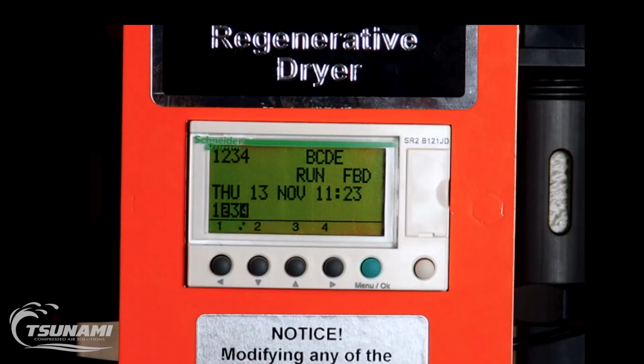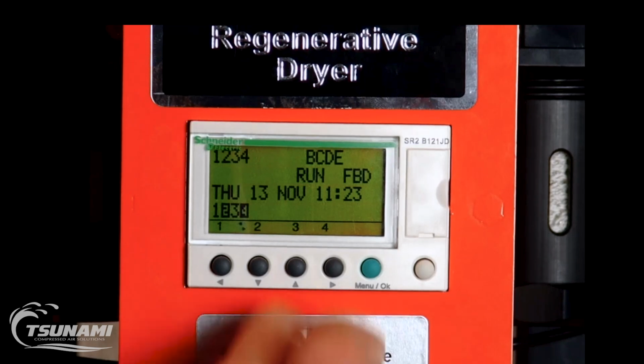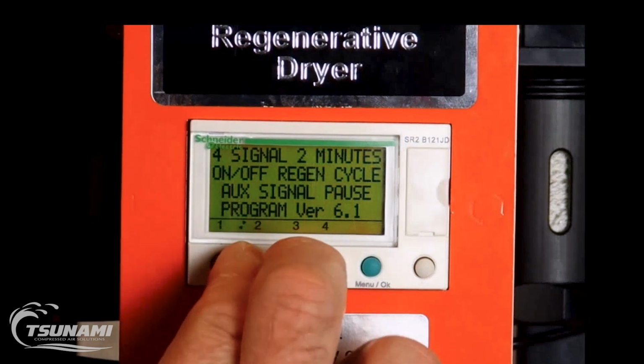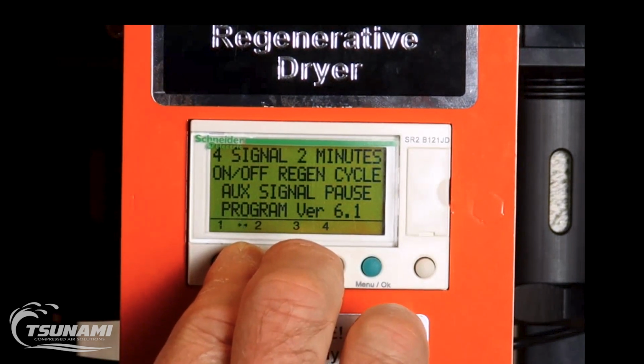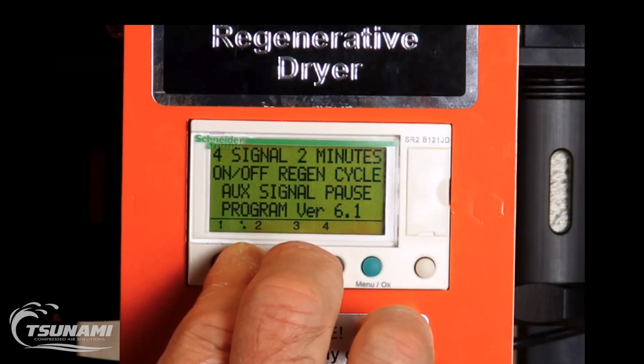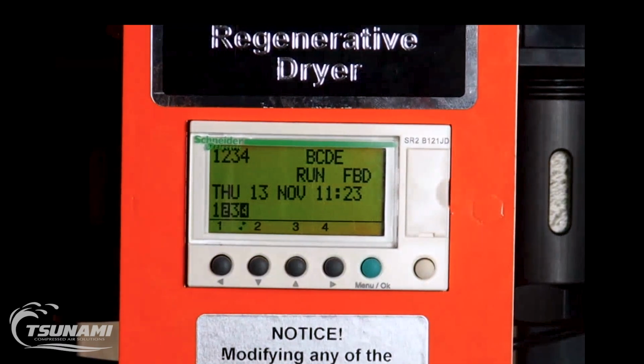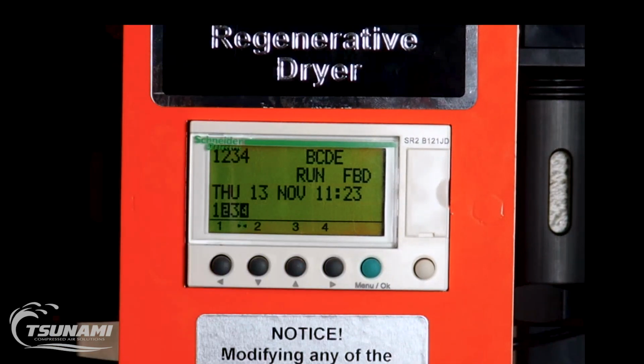So now you can see that we now have 2 outputs showing. So on a 4-tower system, 20 horsepower, we have 2 towers drying and we have 2 towers in regeneration mode. We can also see that by hitting the middle 2 buttons and it will say 4 signal, 2 minutes on-off regen cycle, auxiliary signal pause. So what that's telling us is it's still on a 2-minute cycle. So 2 towers will be drying, 2 towers will be regenerating. And then in 2 minutes, 1 and 3 outputs will highlight, 2 and 4 will go into that drying mode.